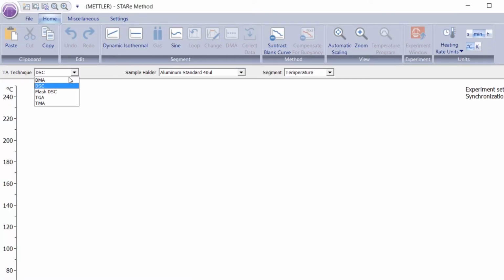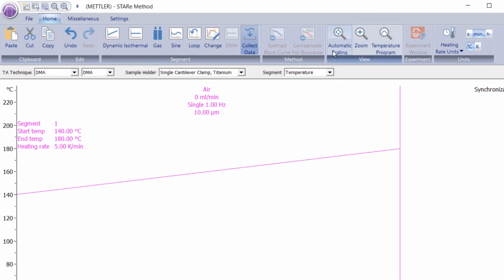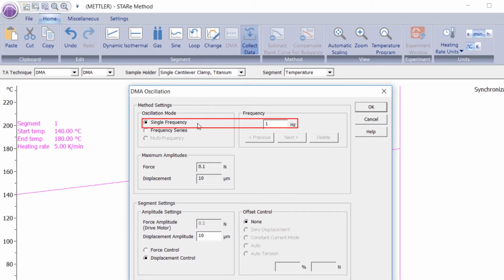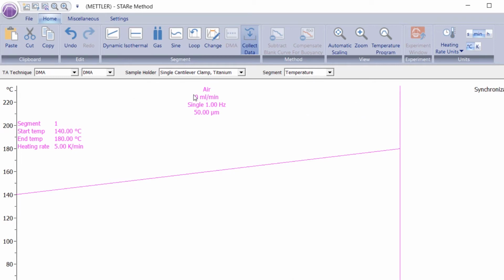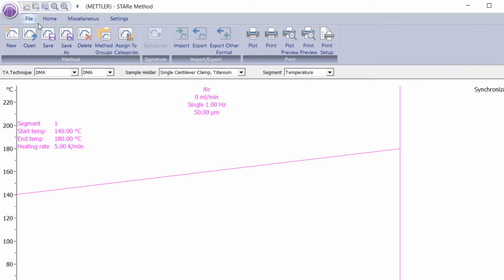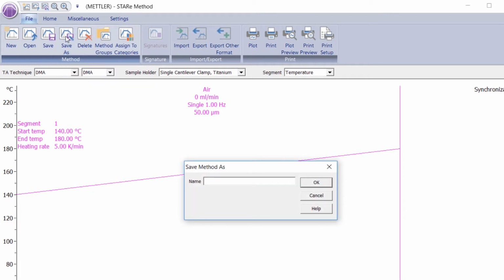In a method window of the STARe software, prepare a single cantilever method with a dynamic segment heating from 140 degrees Celsius to 180 degrees Celsius at 5 Kelvin per minute. Select single frequency, 1 Hz, and enter the displacement amplitude, 50 micrometers. Save this method with the proper file name, DMA1 temperature calibration.